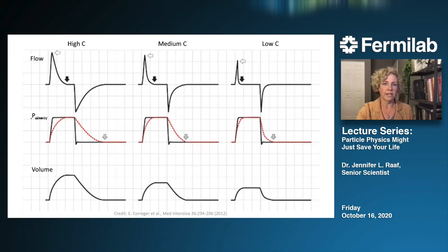So now let me show you how the MVM performed. I'm just showing you one example of the many breathing tests that were required by that international standard. In this test, the ASL 5000 breathing simulator is set to act like a completely passive patient whose lungs and airway have a resistance of 20 in units of pressure over flow and a compliance of 20 in units of volume over pressure. And that's the text written in light blue at the bottom of the graph. Those are not very extreme cases, which you may recognize because of what we just looked at with the effects of changing resistance and compliance on the last two slides.